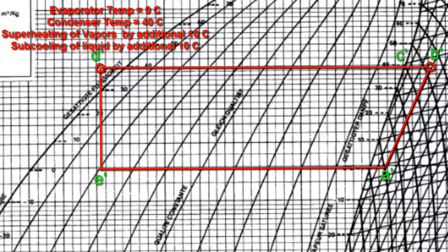The point in the sub-cooled region is now identified, and the temperature of the refrigerant leaving the condenser in the sub-cooled state is at 30°C. Here we have the cycle representing both superheating and sub-cooling. We clean up the extraneous lines and identify the points E-dash, A-dash, B-dash, C-dash, and D-dash representing the superheated and sub-cooled states on this chart. Let's also look at an animation showing how this cycle can be represented on a pH diagram.